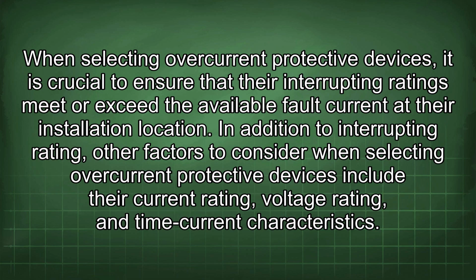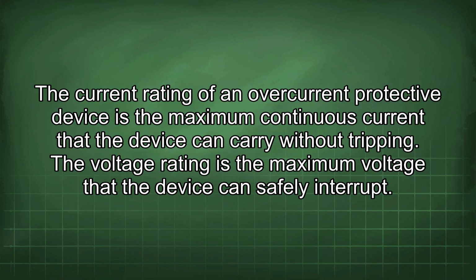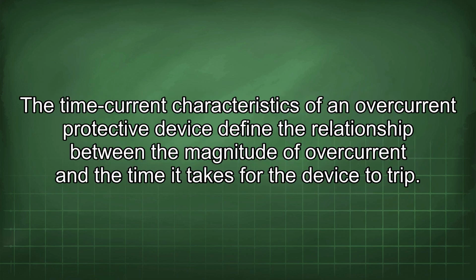In addition to interrupting rating, other factors to consider when selecting overcurrent protective devices include their current rating, voltage rating, and time current characteristics. The current rating of an overcurrent protective device is the maximum continuous current that the device can carry without tripping. The voltage rating is the maximum voltage that the device can safely interrupt. The time current characteristics of an overcurrent protective device define the relationship between the magnitude of overcurrent and the time it takes for the device to trip.